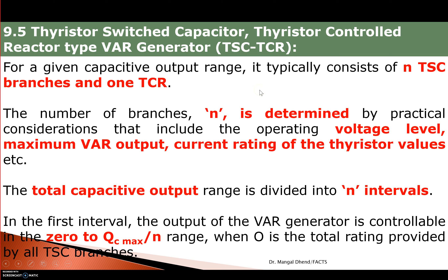Whenever we consider a capacitor, TSC means the capacitor will be switched. TSC stands for Thyristor Switched Capacitor, because a capacitor cannot be controlled with firing angle. There are limitations we have already discussed. The capacitor will give step control and the reactor will give variable control. The TCR will be controlled by controlling the firing angle of the reactor.